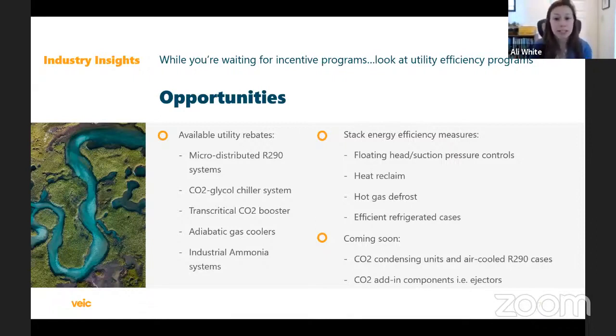And then coming down the pike, what we're really excited about is CO2 condensing units. We've seen some manufacturers breaking into the US market and claiming energy savings over a 404A condensing unit. And so we're excited to do some pilot projects and verify those energy savings. There's also some manufacturers making air-cooled R290 cases that still have good energy savings and don't include that water loop pumping penalty. And as I mentioned, CO2 add-ins like ejectors, parallel compression, mechanical subcooling, those all hold a lot of opportunity. And while they're designed for warmer ambient climates, they can achieve energy savings in any climate.